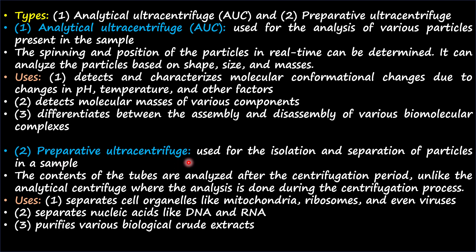Preparative ultra centrifuge is used for the isolation and separation of particles in a sample. The contents of the tubes are analyzed after the centrifugation period, unlike the analytical centrifuge where analysis is done during the centrifugation process. That means in preparative ultra centrifuge, you can detect or identify something only after the centrifugation process is over — you cannot detect anything in real time. That is the main difference between AUC and preparative ultra centrifuge.